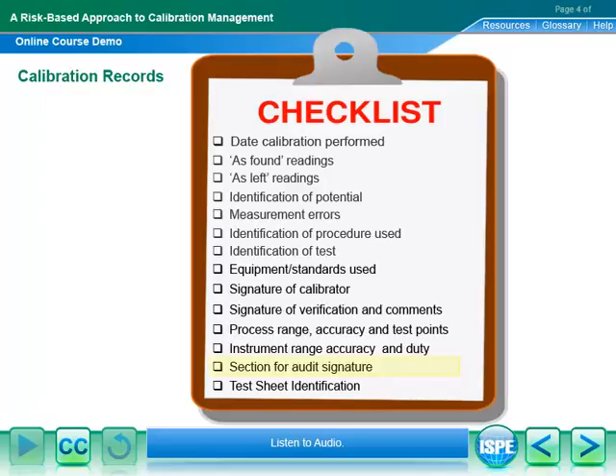It is generally expected for audit purposes. The audit section for signature is optional. Some companies just use a comments section to indicate that an audit has been conducted. It is not expected that this would occur on more than a sample of the calibration certificates.